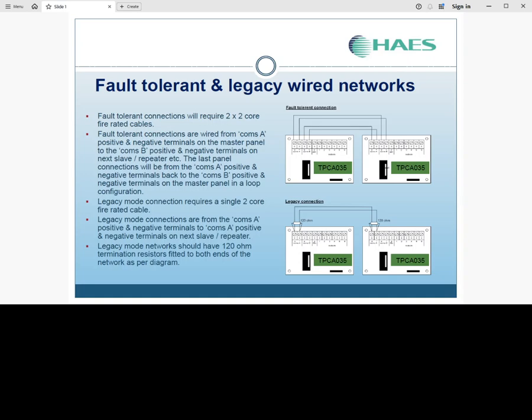For legacy mode connections, these require a single 2-core fire-rated cable. Legacy mode connections are made from the COMS A positive and negative terminals to the COMS A positive and negative terminals on the next slave or repeater. Legacy mode networks should have a 120 ohm termination resistor fitted to both ends of the network as shown in the diagram to the right.